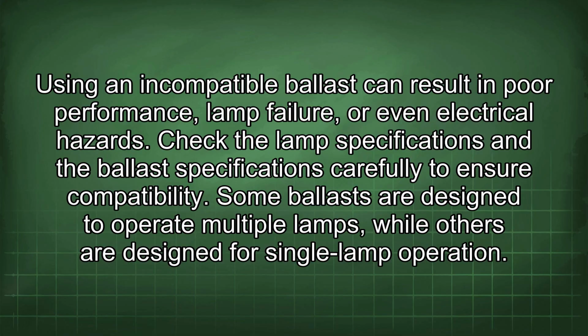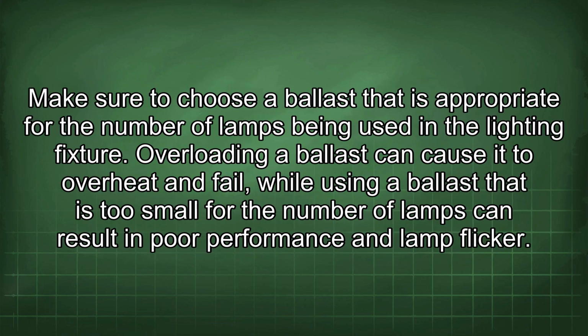Some ballasts are designed to operate multiple lamps, while others are designed for single lamp operation. Make sure to choose a ballast that is appropriate for the number of lamps being used in the lighting fixture. Overloading a ballast can cause it to overheat and fail, while using a ballast that is too small for the number of lamps can result in poor performance and lamp flicker.